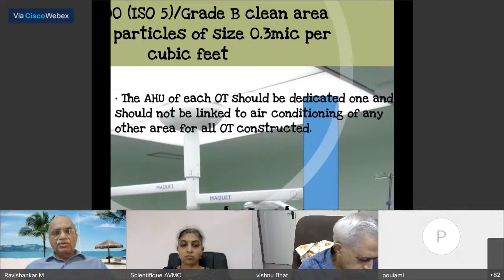During non-functional hours, the AHU blower should be operational round the clock. It should not be switched off - that's the most important thing. You might cut down, you may not control the temperature, but you might run it. You may not have 20 to 30 air exchanges, you might reduce it down to 3 to 4 air exchanges per hour, but it should be continuously on so that there is no stagnation of air inside the operation theater. That's the most important thing.